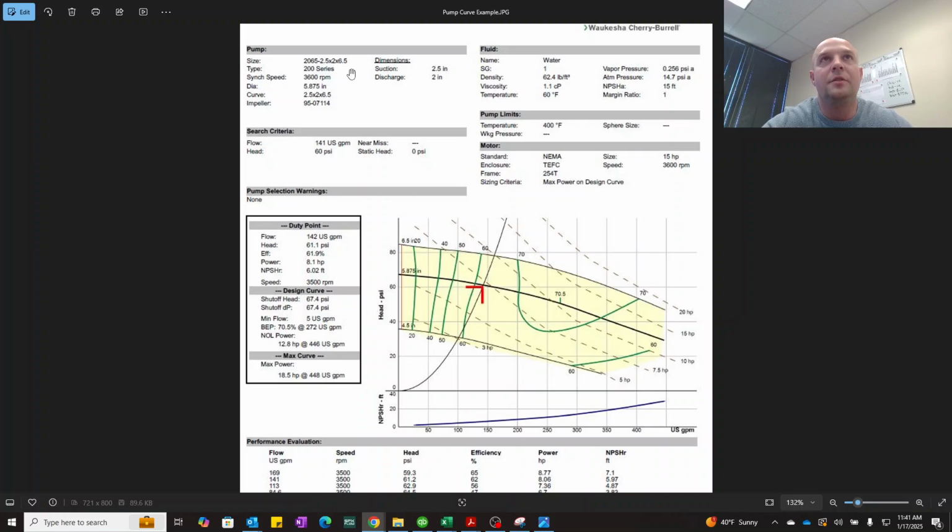We're going to use a 5.875-inch impeller because it fits on this curve real nice. It says we choose a 15 horsepower motor, but looking at our power draws down here as well as the curves, I'm probably going to be a little more aggressive and go with the 10 horsepower motor, not the 7.5. And we'll put it together for the customer, ship it to them. This will be a great CIP supply pump for them. We'll just use a Type 1 seal, carbon and ceramic seal, and it'll be another happy customer and successful pump installation.